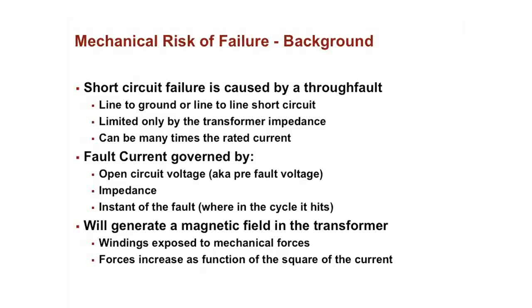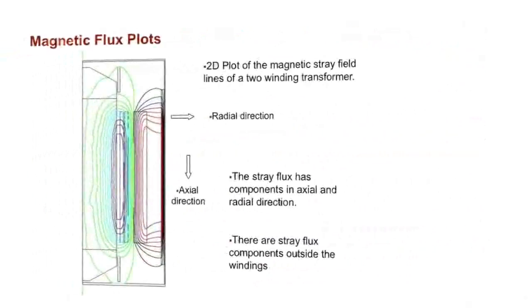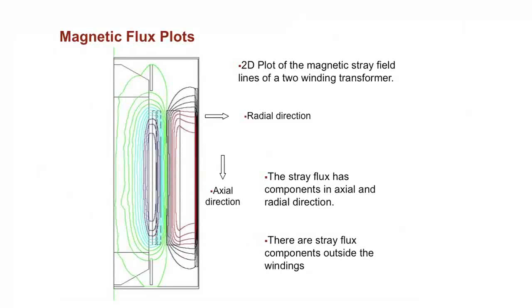Okay, and then this fault current, as I said, is limited by the impedance. It also matters what the voltage was at the time, and at what instant in the cycle the fault hit. So the end result of all this is that you have much more magnetic flux in the transformer, and this causes huge mechanical forces in the transformer. So this is a flux plot of a transformer.